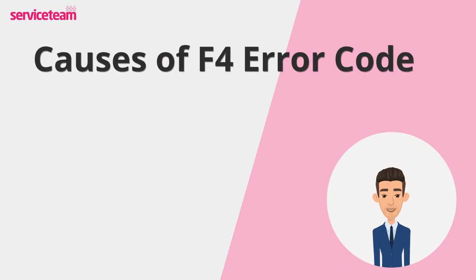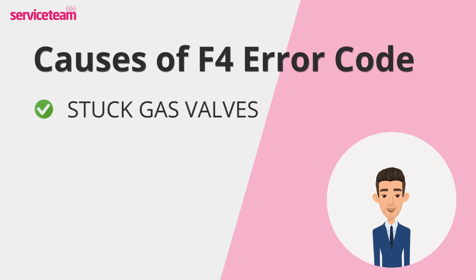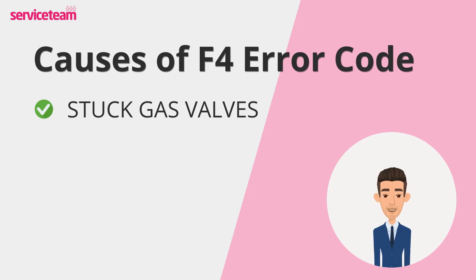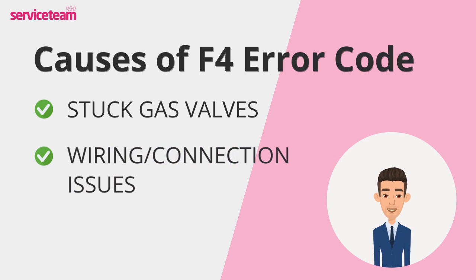Let's see what causes the F4 error. Stuck gas valves are one reason for the Viessmann F4 fault. Gas valves regulate the flow of gas into the boiler — normally closed, they open when heating is activated, allowing gas to flow. If stuck, they prevent fuel from reaching the boiler, stopping the flame from lighting. Faulty wiring or poor connections can also cause gas valves to send inaccurate signals to the PCB, triggering an F4 lockout. Even if the flame is lit, the PCB might fail to detect it due to these connection problems.